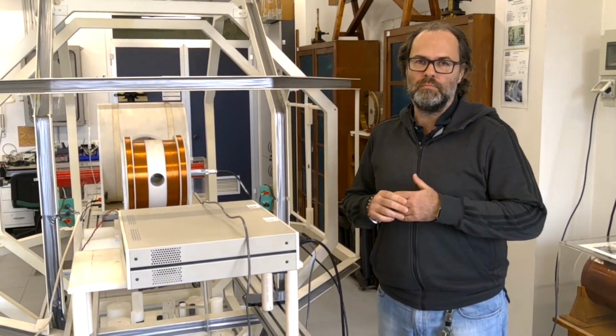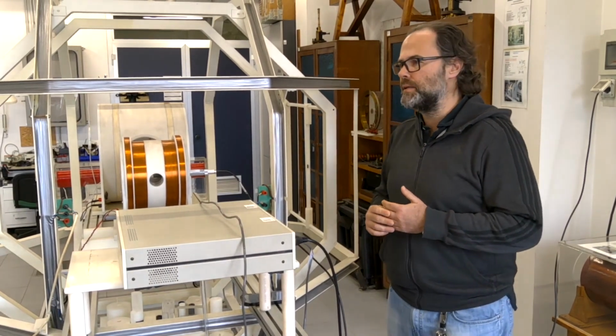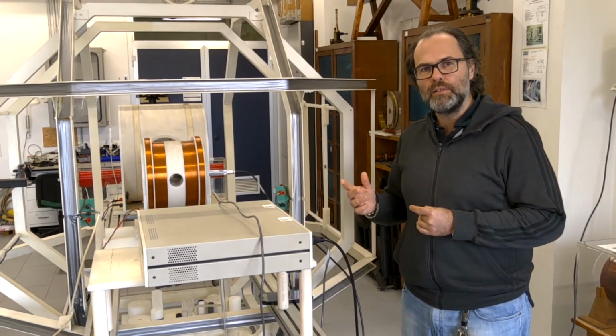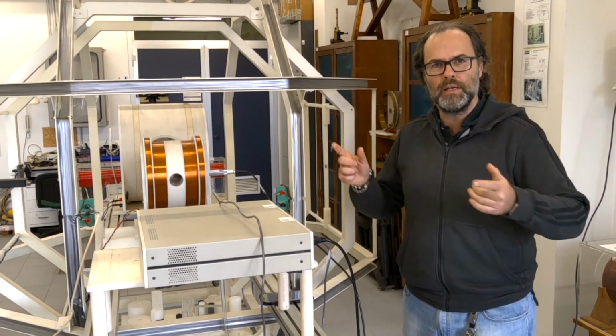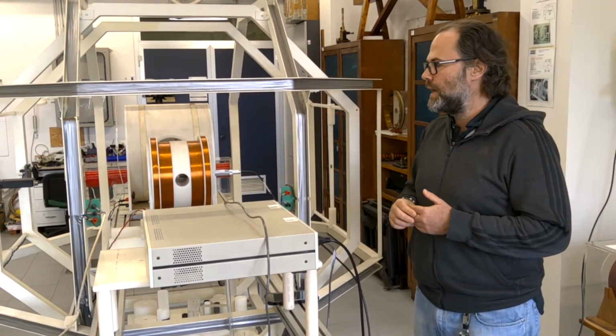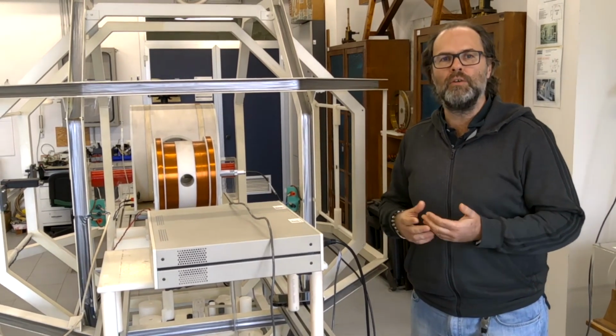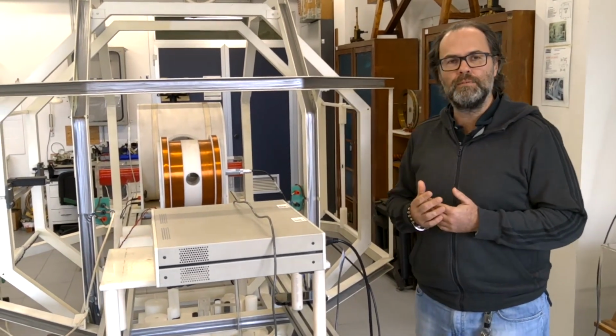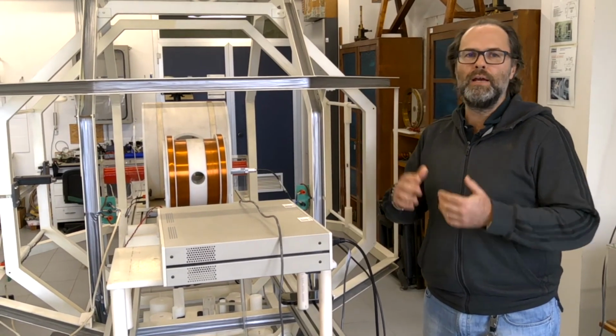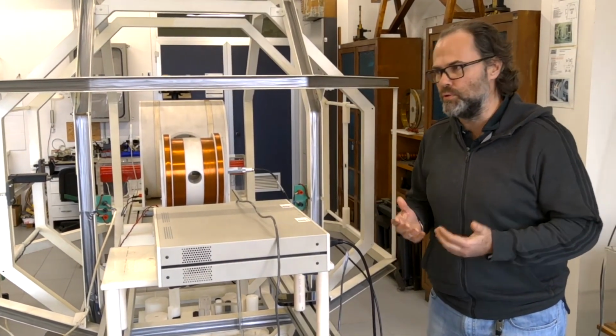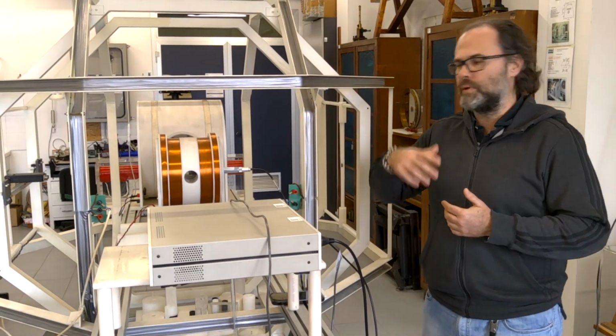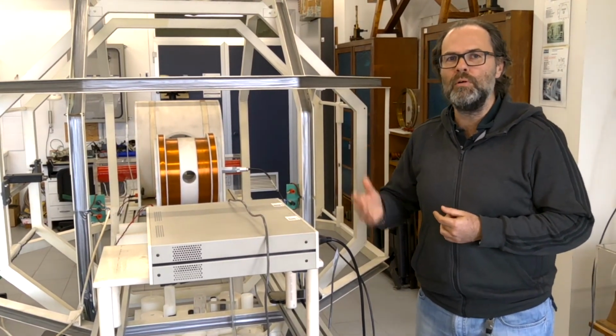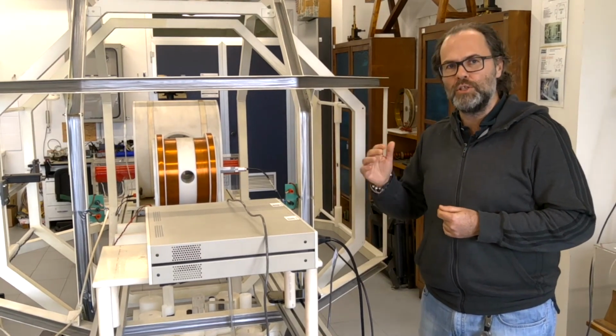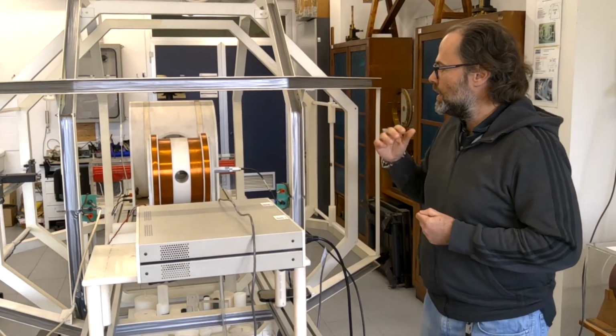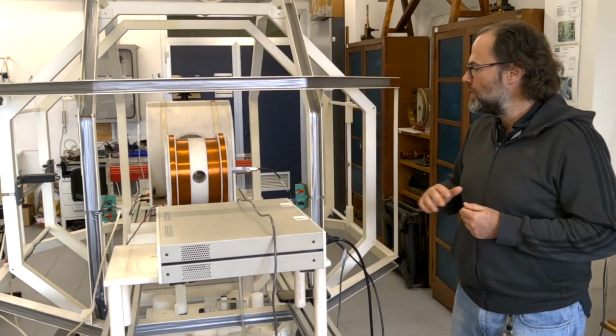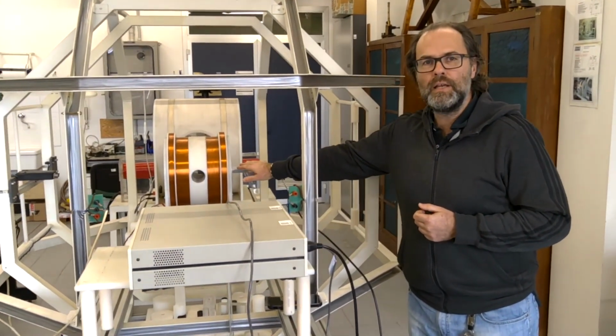Contrary to what many people expect, the Earth magnetic field is not constant over time. It is a vector that has components along all 3 directions in the space, X, Y, and Z, and its intensity and direction change over time. So the compensation of the Earth magnetic field has to be done before every calibration experiment that we do. Because if we do it today and repeat the calibration tomorrow, the Earth magnetic field vector will have changed both intensity and direction. In order to compensate for the Earth magnetic field, we use a Flux-Gate 3-axial sensor.